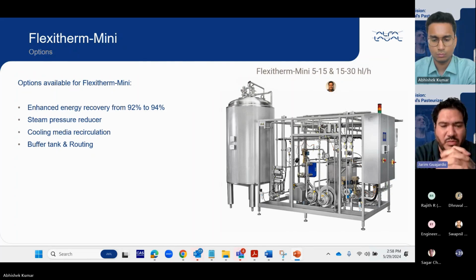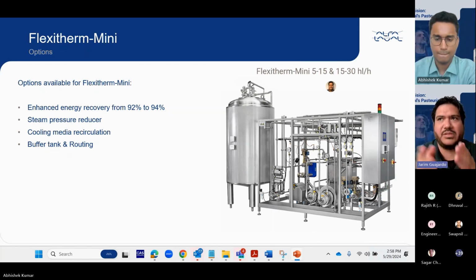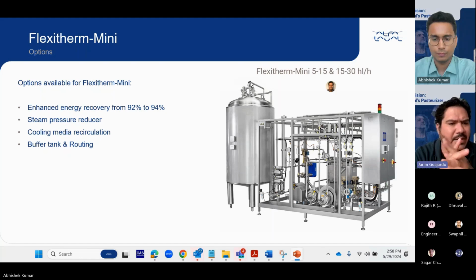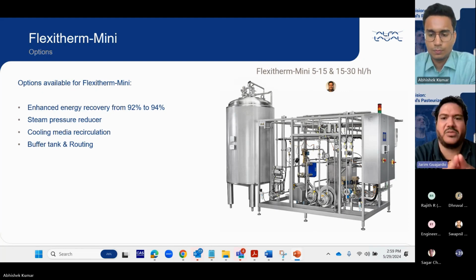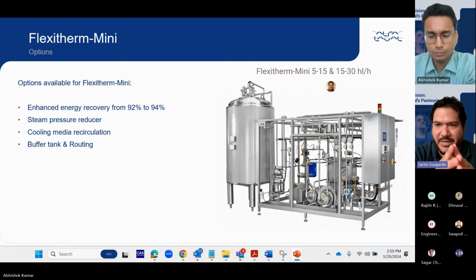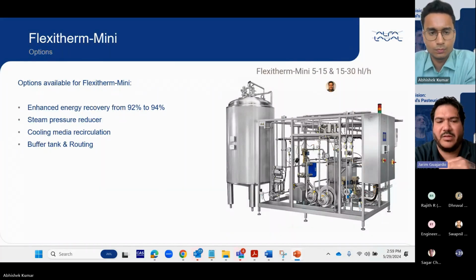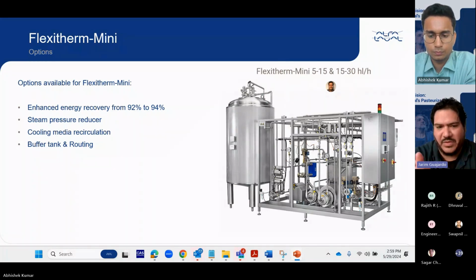We have the possibility to help with a pressure reducing station in case you have a really high pressure inlet. Also, we have cooling media recirculation, which is important when you have very cold glycol, to make sure the beer doesn't freeze inside the system. So we have a recirculation pump to avoid this, and of course the buffer tank and routing. As I mentioned, if you already have your own buffer tank or preferred supplier, you're welcome to use that, and we'll help with the routing and what's needed to control it properly. Otherwise, we offer the whole package ourselves with the buffer tanks.